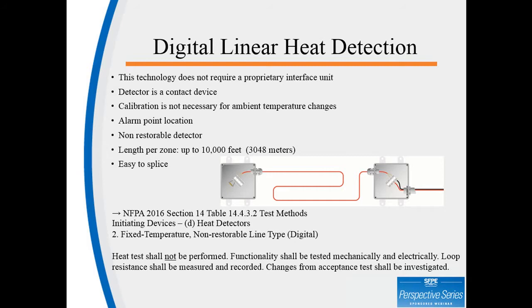Fixed temperature, non-restorable, line type, digital. Heat tests shall not be performed. Functionality shall be tested mechanically and electrically. Loop resistance shall be measured and recorded. Changes from acceptance test shall be investigated.